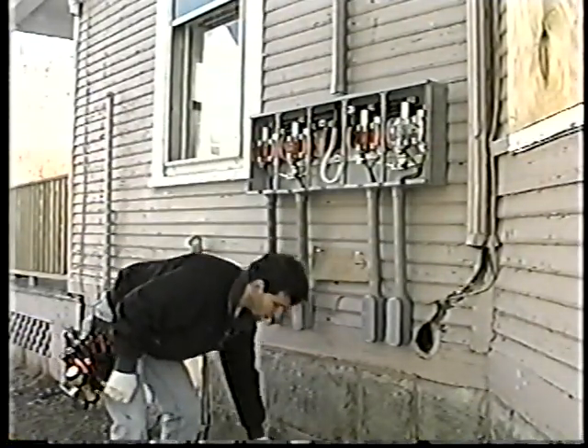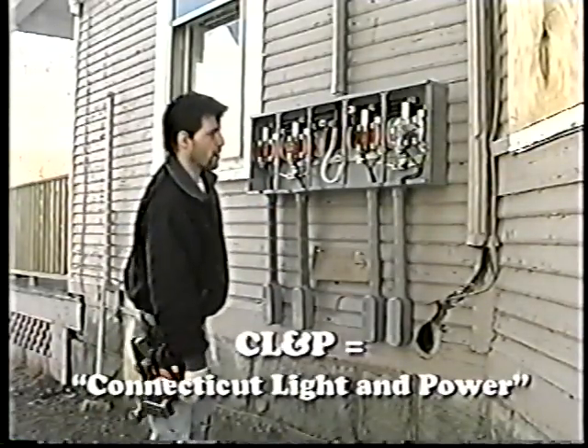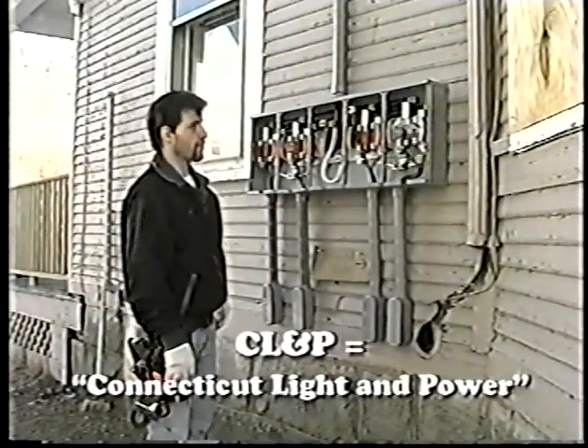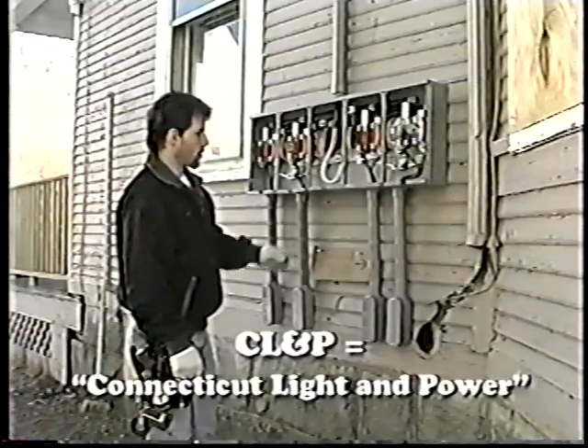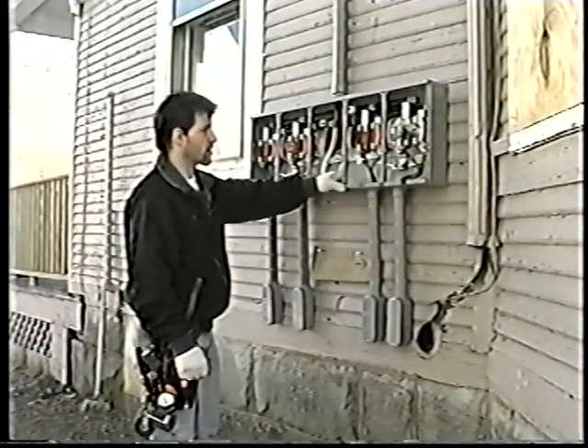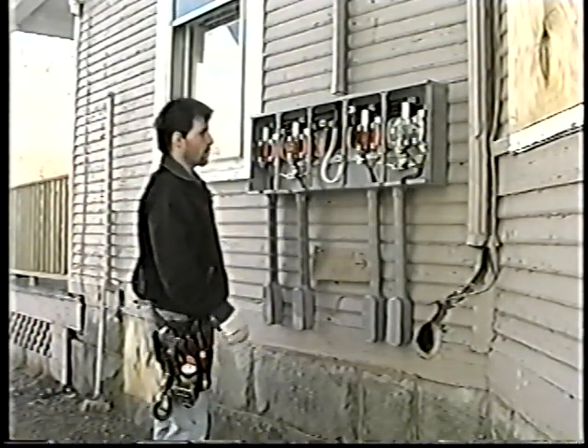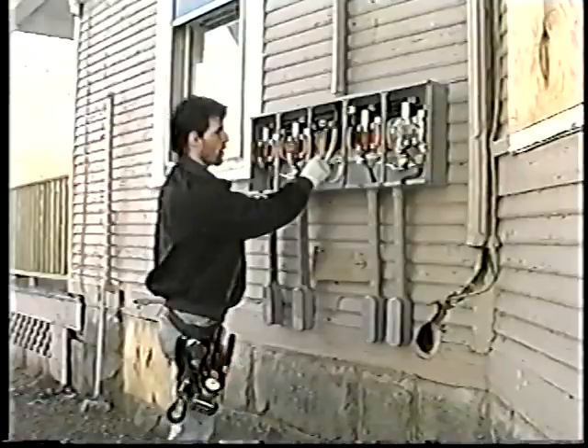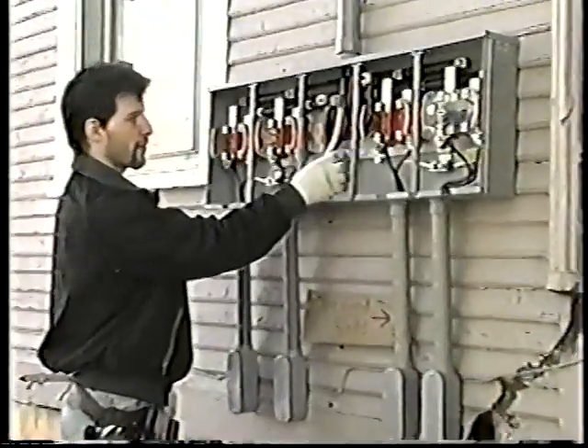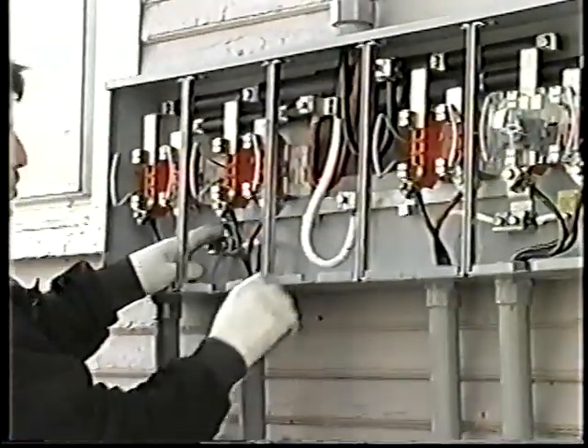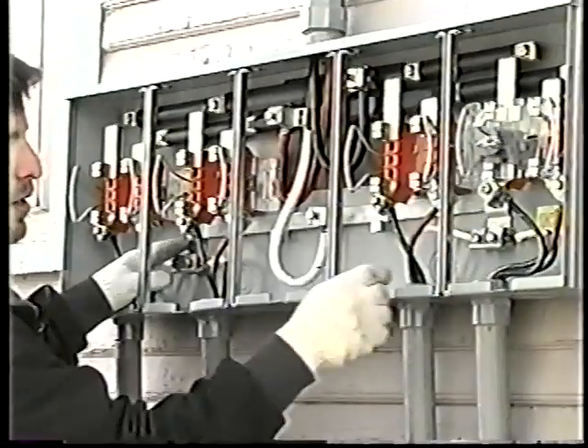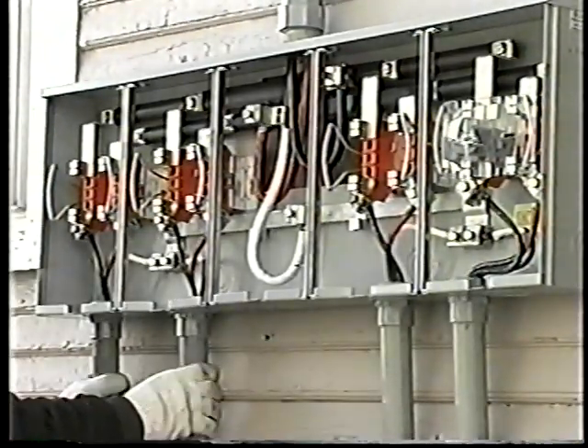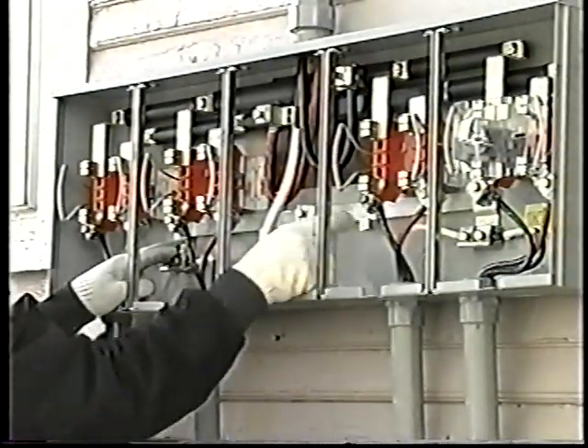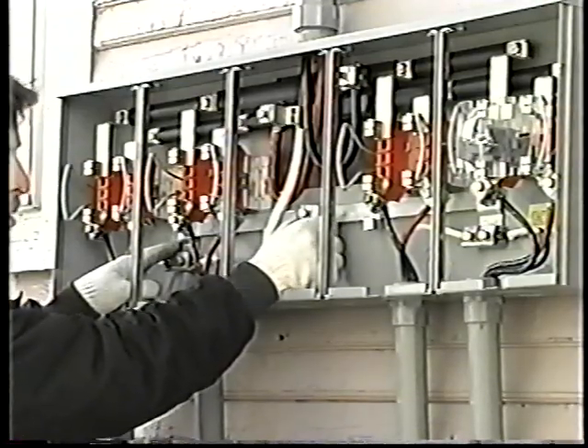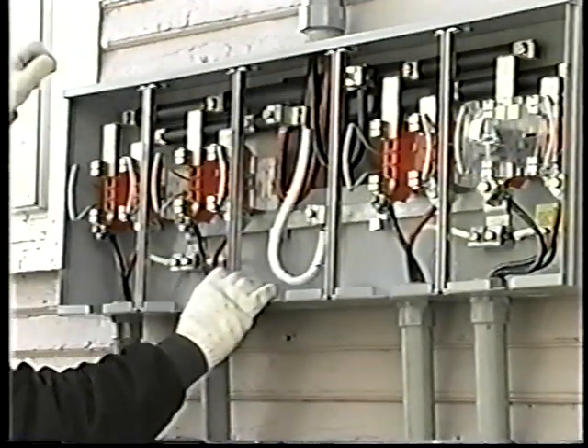You do not want to go into this panel, and most of the time CL&P has it locked. If they catch you in here, there's actually a criminal offense against you. But anyway, we've got a white wire which is called our neutral wire. It feeds this main lug, which goes across the whole bottom of the meter socket, and each one of our pipes has a white wire also, which comes up and connects to other lugs that are also attached to that main bar. And the same thing works for the top.